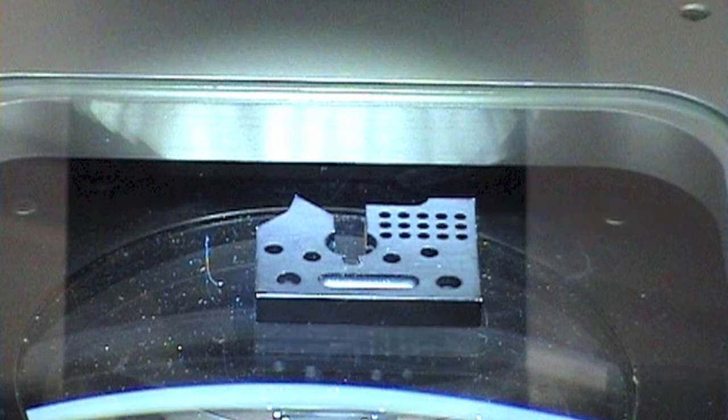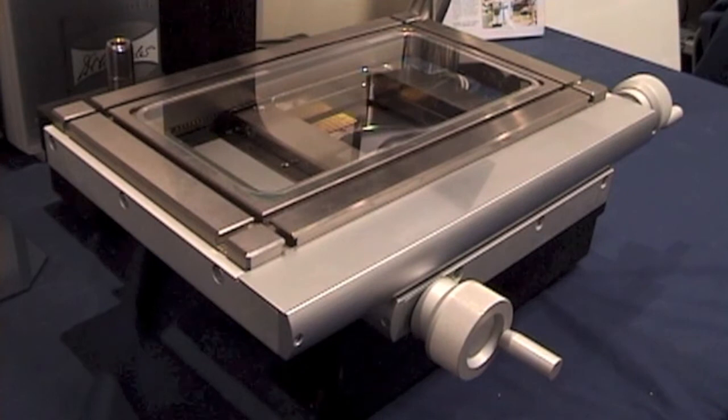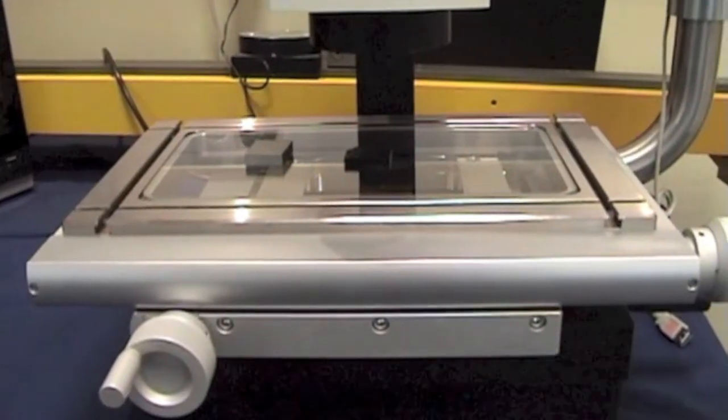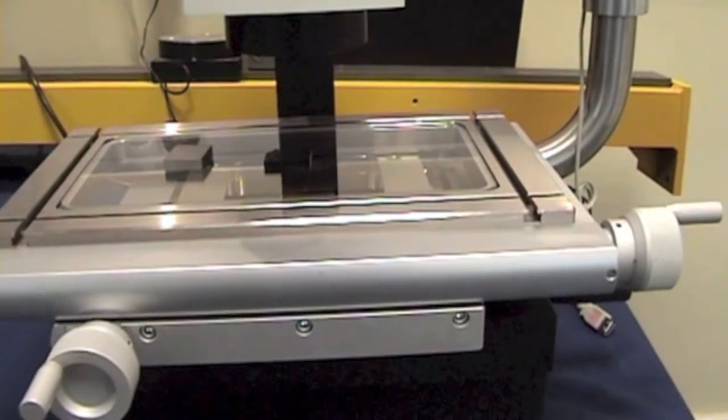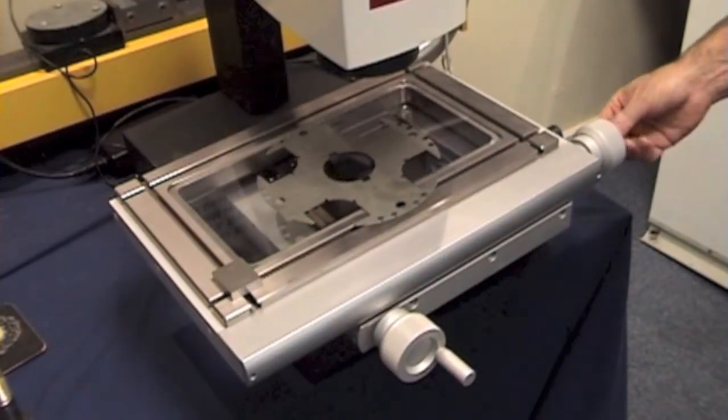For larger components, this can alternatively be supplied in conjunction with an XY stage which is movable anywhere in its range and is fitted with a dual Heidenhain grating with one micron resolution. This means you can accurately assess large geometry to high accuracy.